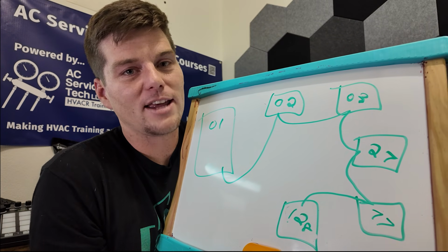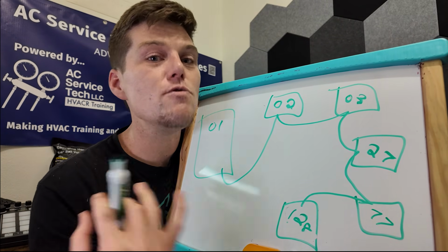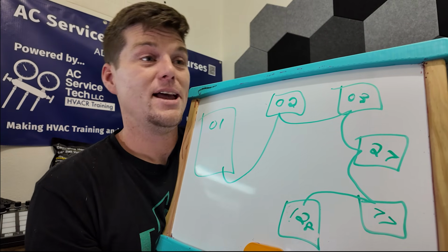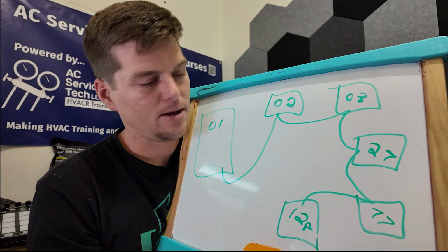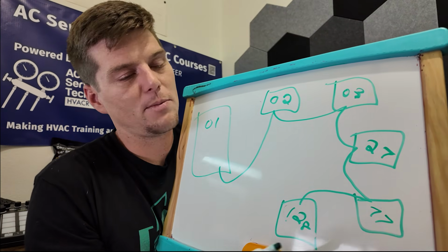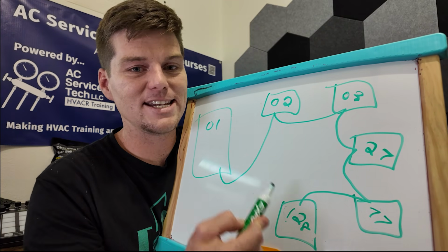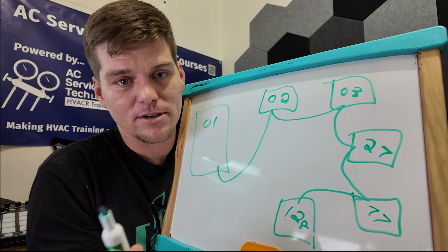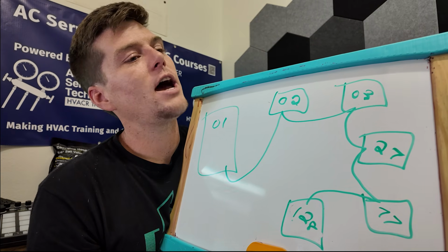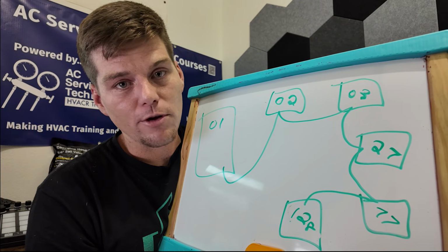We know it's not communicating. That's why it has a U4. So let's move on. So you haven't done the service tools, and maybe you did the count, but you're not going to hang your hat on it as accurate. People get frustrated with this part because they assume what it sees is accurate to what's happening right now. Again, just a snapshot. So now the approach here is measuring output voltage.